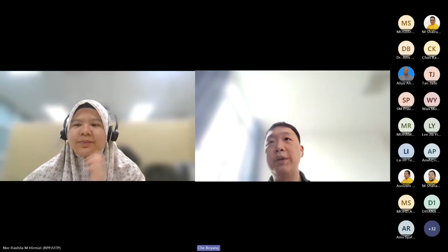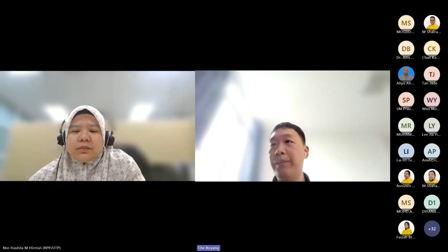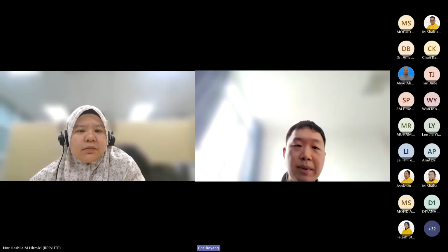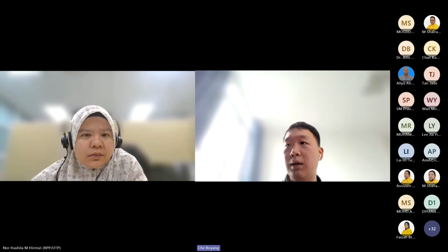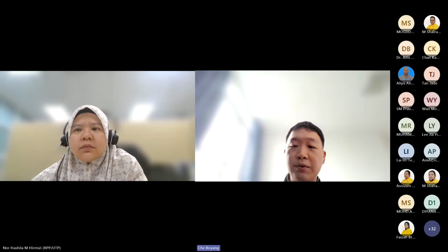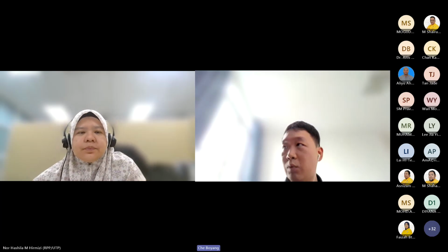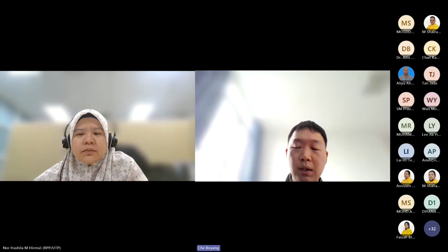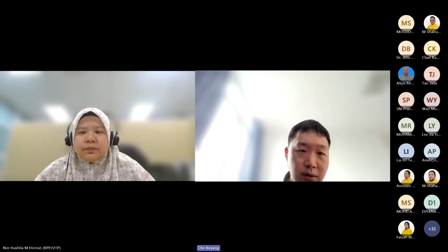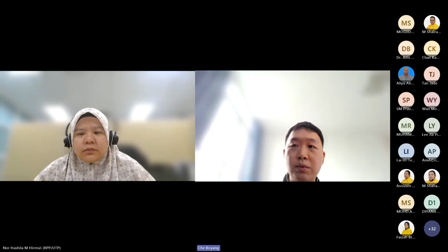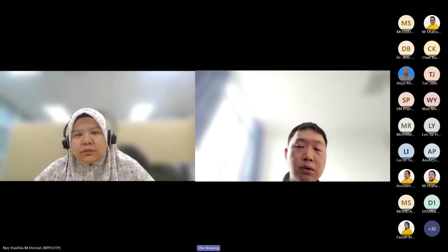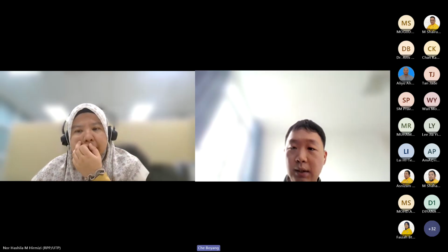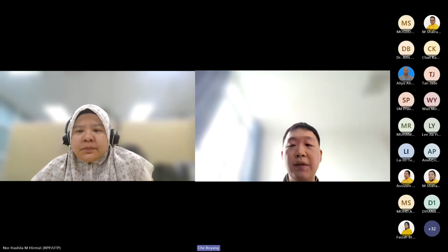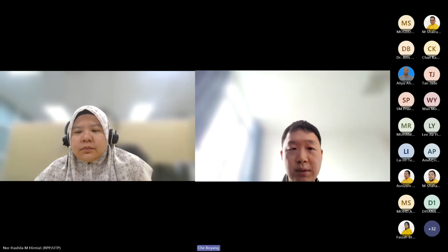Yeah, that's a very good question. Usually for Raman mapping, not only 3D, even the 2D one, it actually takes longer compared to a single point measurement, because Raman mapping is scanning an area, point by point within this area. So many points will be scanned, and on each point you have one spectrum. The total time of the Raman imaging depends first on how many points you want to scan within this area, which depends on the step size in X and Y. If you have a larger step size, you will have fewer points and faster speed. But if you want a very good quality image with good resolution, you increase the number of points, and of course the total measurement time increases.